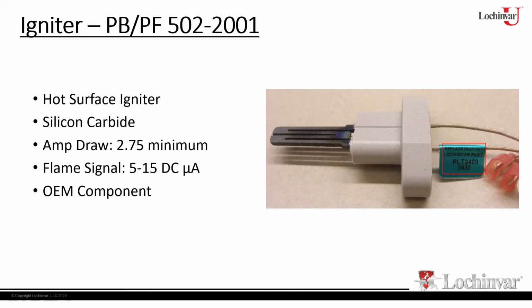Now, once we energize the gas valve, we've got a 5-second window to prove the burner flame in. The control module will then switch and use the igniter as your flame sensor. So you have a 5-second window. The first 4 seconds will keep the igniter energized. And in that last second, it switches to look for a DC microamp signal. All right, the DC microamp signal I'm looking for is a minimum of 1 microamp. I have to have a minimum of 1 to actually prove the burner flame in.